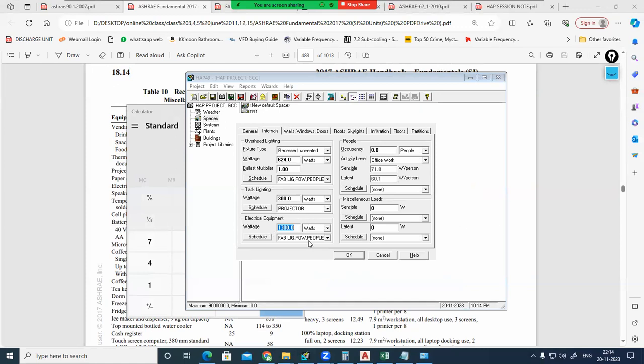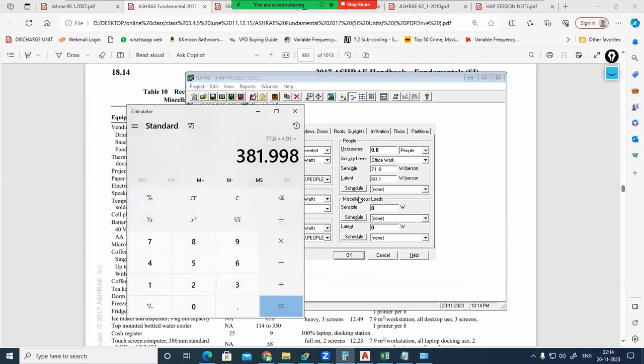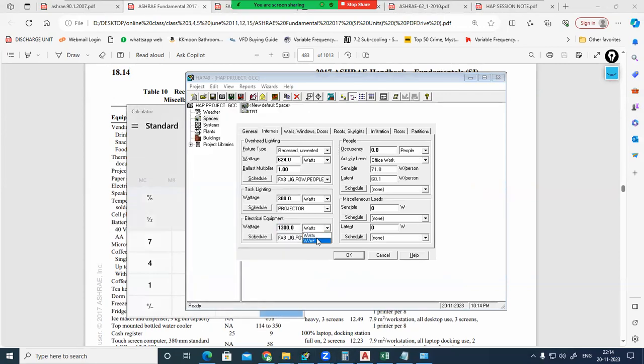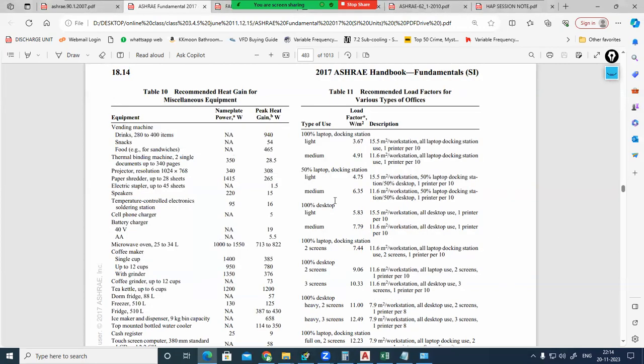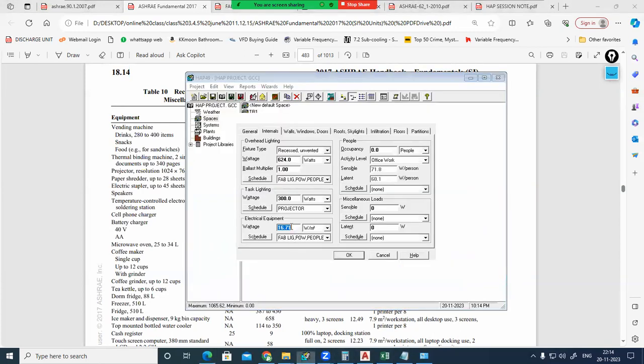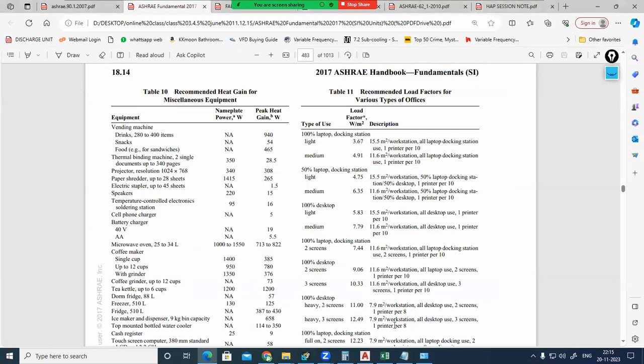But this will be slightly less, comparing to 382. Less only it will come. Sometimes it might be more. But you don't want to do this calculation. Rather, you have to select watt per meter square, 4.91. The remaining calculation the software will do. The software will multiply this 4.91 with the 77.8. Anyway, this is less only, so I'll be going for the previous one.